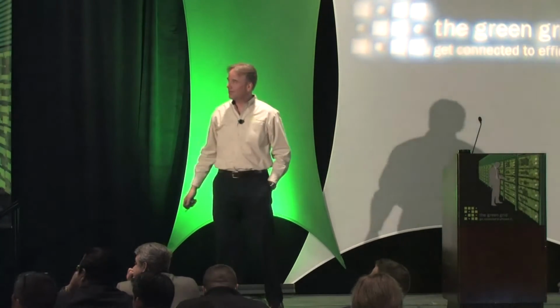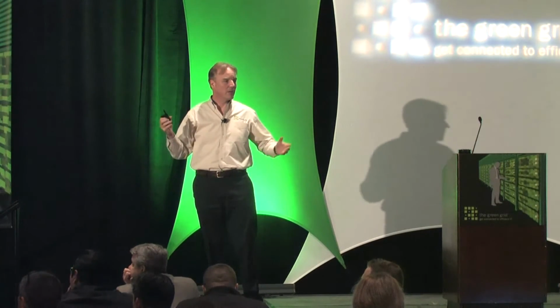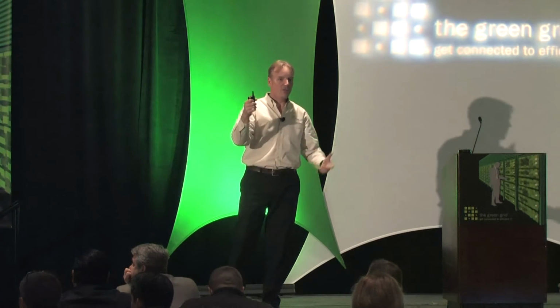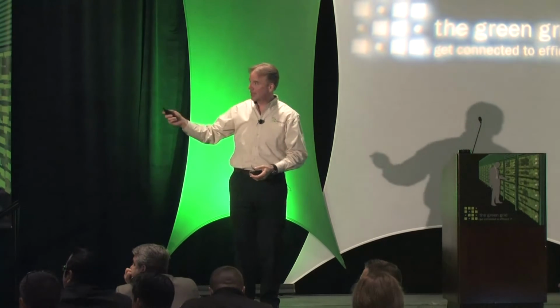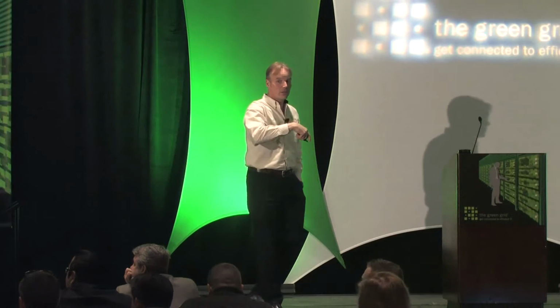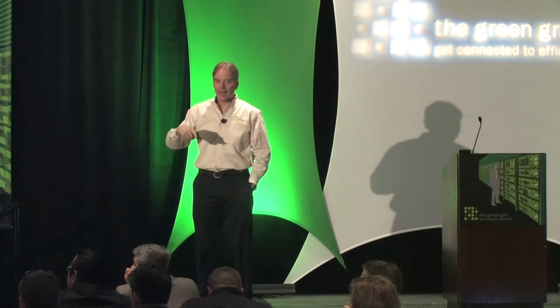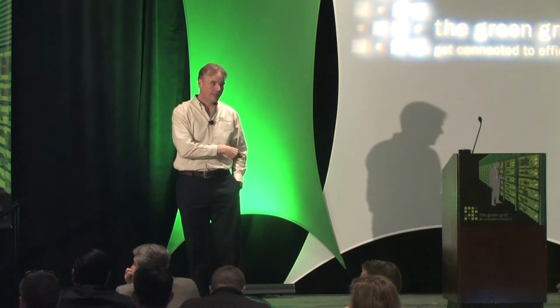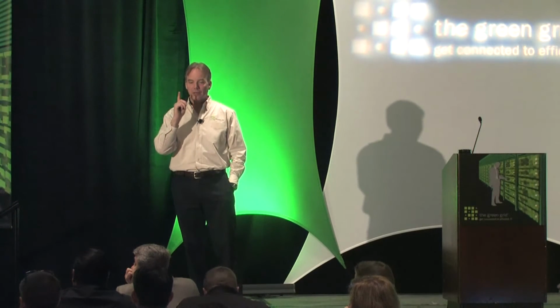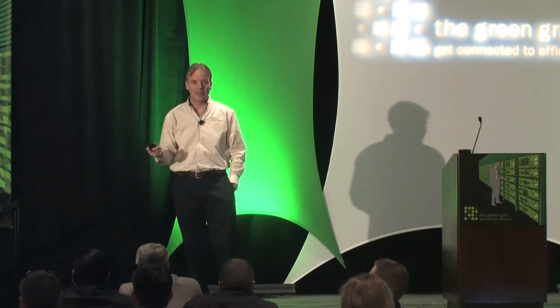This is a cutaway of the building. On the ground floor, we have 220 rack positions. It's a white floor or white space that we can do rack and roll. So that's the standard rack config I was talking about. On the roof, we have containers. The entire site basically is going from 4 megawatts day one, this is IT load, to 12 megawatts over time. Okay, and we have kicked off our next 2 megawatts already. The racks can actually scale from 4 kilowatts to 40 kilowatts average. Note that, because I will have 40 kilowatt average over all of the racks when I hit 12 megawatts.